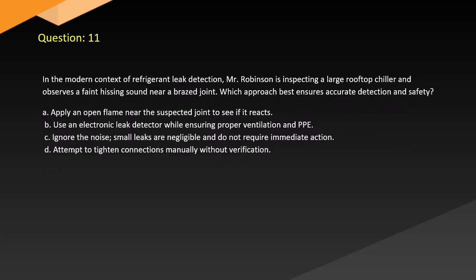Question 11. In a modern context of refrigerant leak detection, Mr. Robinson is inspecting a large rooftop chiller and observes a faint hissing sound near a brazed joint. Which approach best ensures accurate detection and safety? A. Apply an open flame near the suspected joint to see if it reacts. B. Use an electronic leak detector while ensuring proper ventilation and PPE. C. Ignore the noise. Small leaks are negligible and do not require immediate action. D. Attempt to tighten connections manually without verification.